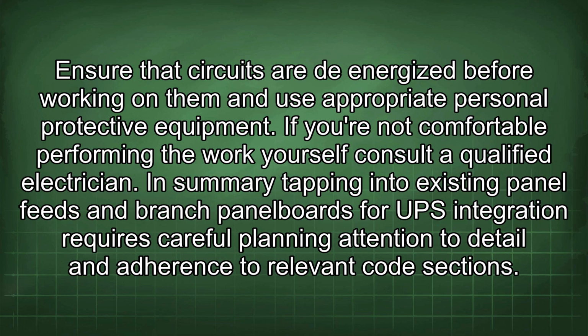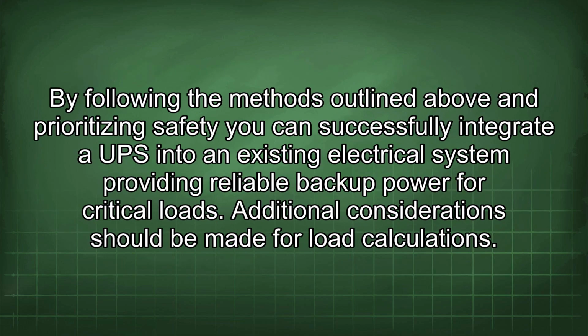In summary, tapping into existing panel feeds and branch panel boards for UPS integration requires careful planning, attention to detail, and adherence to relevant code sections. By following the methods outlined above and prioritizing safety, you can successfully integrate a UPS into an existing electrical system, providing reliable backup power for critical loads. Additional consideration should be made for load calculations.